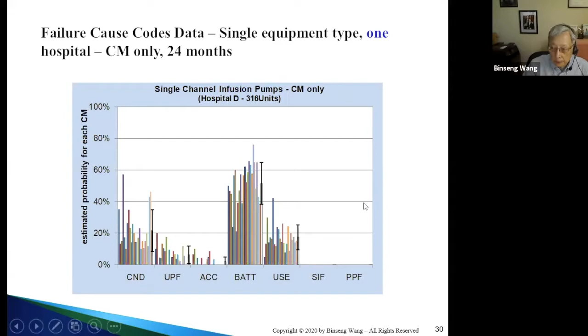When we put the two together, we can use a mathematical way to combine them. We call this the probability of finding a particular class of failure, the annual failure probability, and the combination is shown here. In other words, if I pick up an infusion pump at random, doesn't matter whether scheduled maintenance or corrective maintenance, I know these are the likelihoods of finding the problems here. The last 4 that I mentioned to you, service-induced failure, hidden failure, potential failure, and predictable, preventable failure, are very, very rare. I magnify the scale here to show you that it's very rare, but they can happen and do happen, okay?